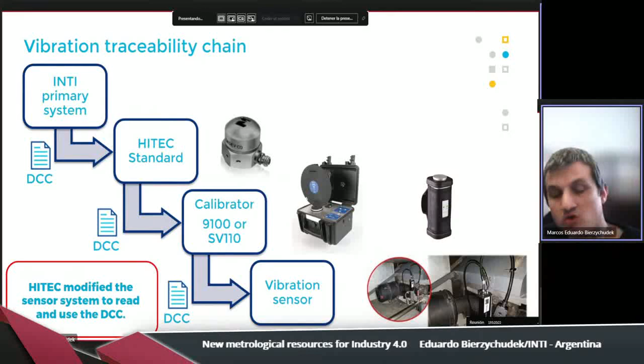Then HITEC wrote the calibration procedure for all this calibration, and now we already have an XML file for this shaker, this little calibrator. It can only work at two frequencies and can be used to perform in situ or remote calibration directly where the sensor is installed. HITEC is working to modify all its software platform in order to integrate the DCC. So when the data measured by the vibration sensor is analyzed, they can correct the data by the DCC, or they can calculate the uncertainty.